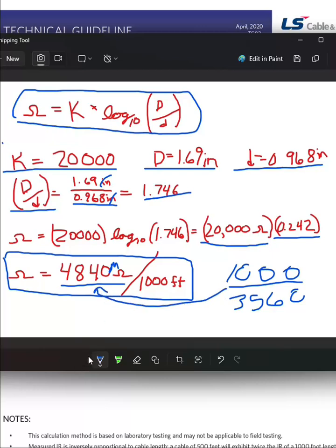And so if we had cable that was 3,560 foot long, our ohmic value should be somewhere around 1,359 megohms, or 1.359 per conductor. So per run. So if you have 5 parallel sets or whatever you have and you're testing them all at the same time, you can compensate and make them parallel, and then you can figure out exactly what your ohmic value should be.